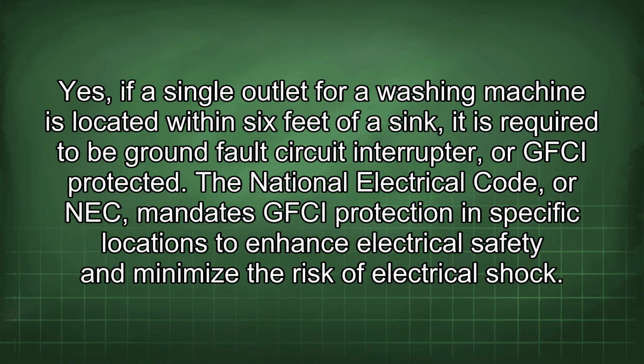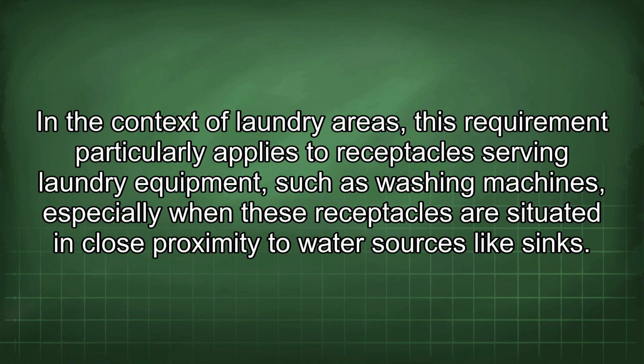Yes, if a single outlet for a washing machine is located within 6 feet of a sink, it is required to be ground fault circuit interrupter, or GFCI protected. The National Electrical Code, or NEC, mandates GFCI protection in specific locations to enhance electrical safety and minimize the risk of electrical shock. In the context of laundry areas, this requirement particularly applies to receptacles serving laundry equipment, such as washing machines, especially when these receptacles are situated in close proximity to water sources like sinks.